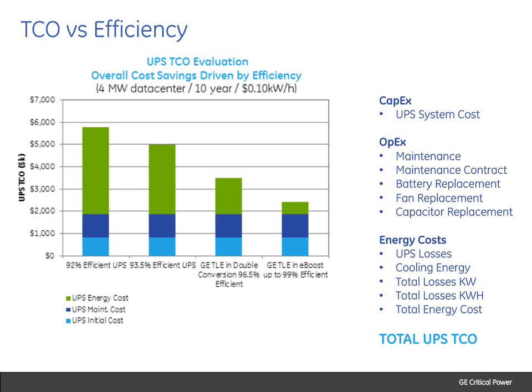Going to the 96.5% double conversion requires more advanced technology, 3-level topologies on the IGBTs, to get double conversion efficiency up to 96.5%. The far right-hand side is our technology called eBoost, a multi-mode or eco mode, where you actually operate the UPS in bypass mode. Those are some of the key technologies that drive these efficiency differences.